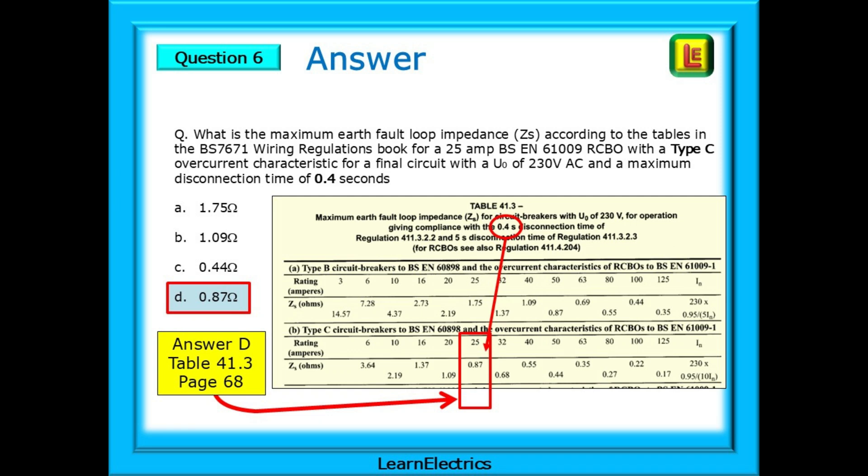Again, look in the index on page 583 for disconnection times final circuits and you will be directed to table 41.1. Since the question mentions tables, it is then just a matter of turning a page or two to find table 41.3 for circuit breakers and RCBOs.